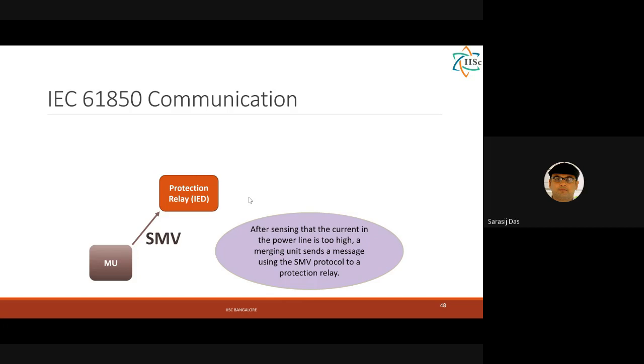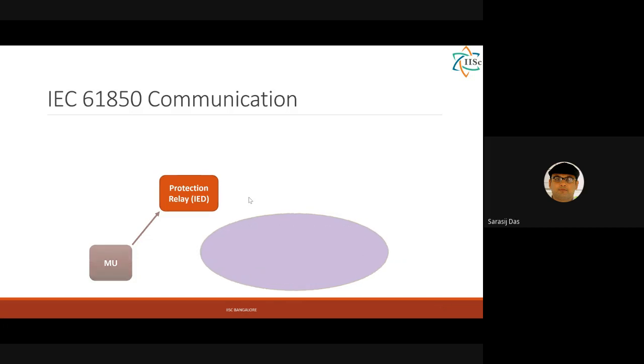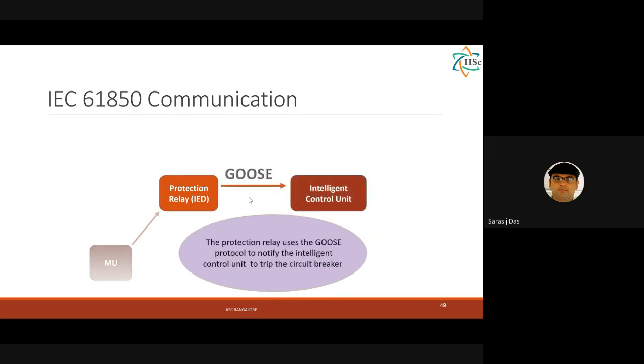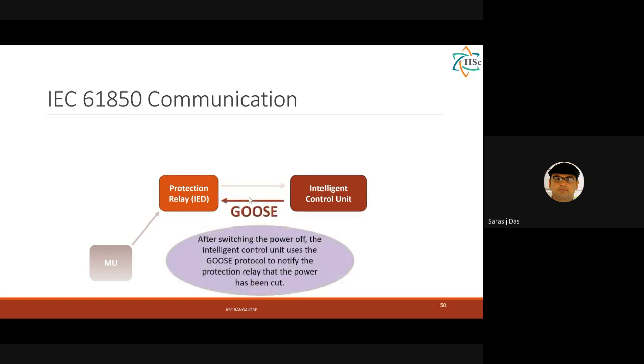Now in the relay, based on those measurements, it calculates whether there is a fault or not. If there is a fault, then a trip signal is sent to an intelligent control unit which basically controls the circuit breaker, and this trip information is sent via goose message. Once the circuit breaker is tripped, the status of the circuit breaker is again sent back to the protection relay via goose message.